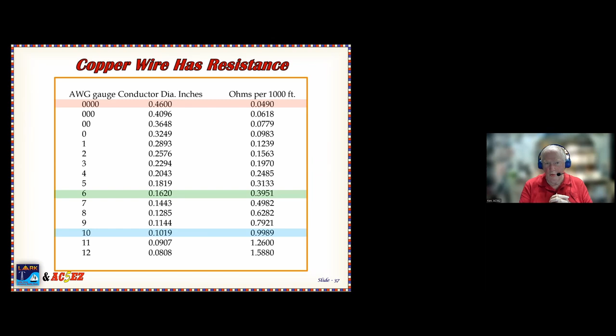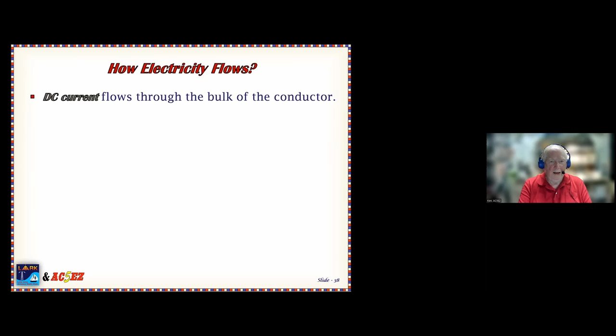Now, I highlighted the 0000 wire for one particular reason. That's probably the largest wire that you can get, and its diameter is only less than half an inch, 0.46 inches. And I want to show you something about how electricity, well, you know how electricity flows. DC flows through the body of the core of the conductor, and AC flows on the outside skin of the conductor. Well, when you're grounding, you're talking about AC. This could be lightning, it could be static discharge. It's going to be an AC component. Now, it doesn't mean 110 volts AC. It just means it is an AC type voltage, and it's going to travel on the surface of whatever conductor you're using.